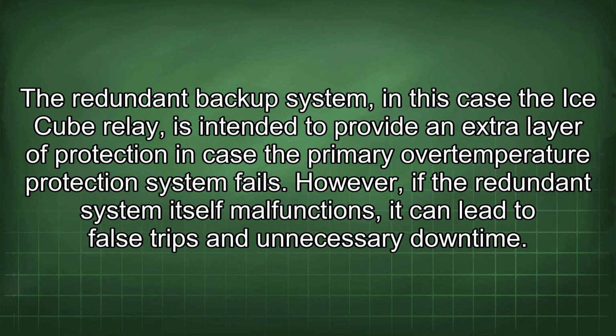The redundant backup system, in this case the ice cube relay, is intended to provide an extra layer of protection in case the primary overtemperature protection system fails. However, if the redundant system itself malfunctions, it can lead to false trips and unnecessary downtime.